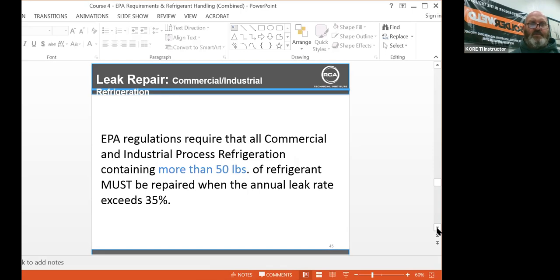Leak repair in commercial and industrial refrigeration. EPA regulations require that all commercial and industrial process refrigeration containing more than 50 pounds of refrigerant must be repaired when the annual leak rate exceeds 35%.